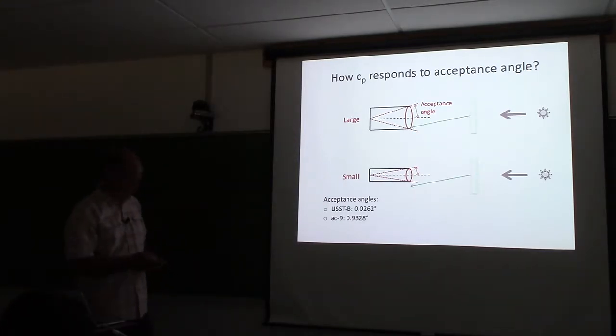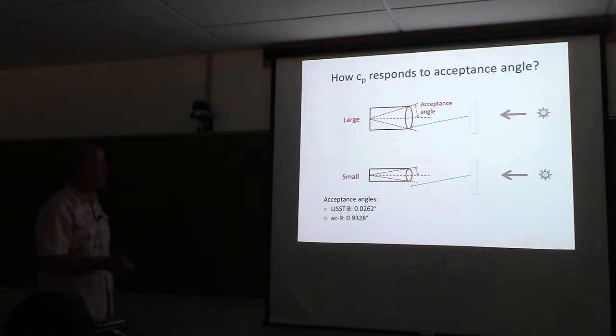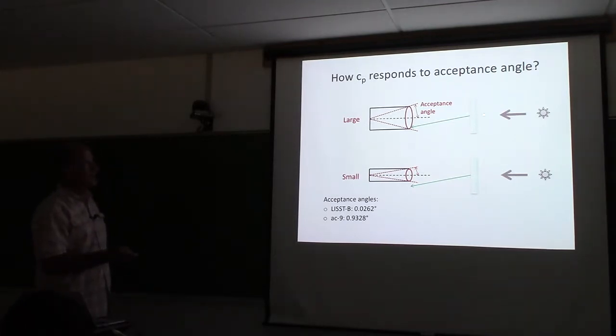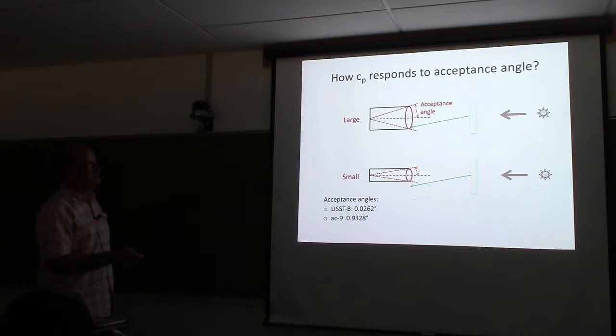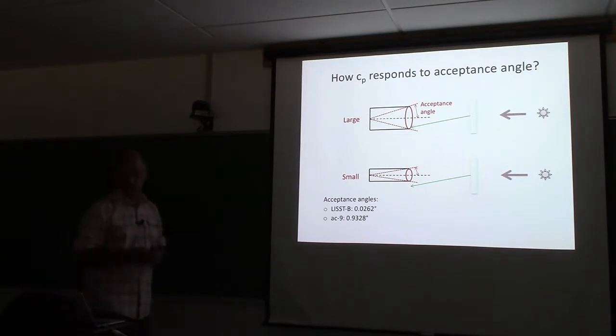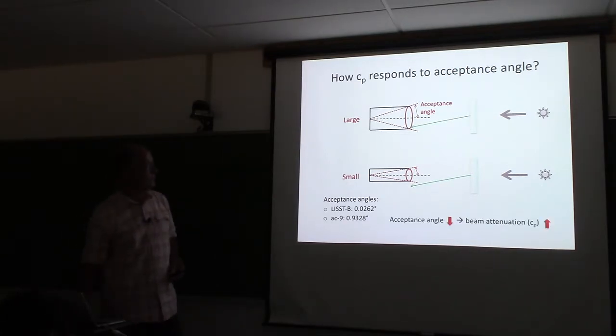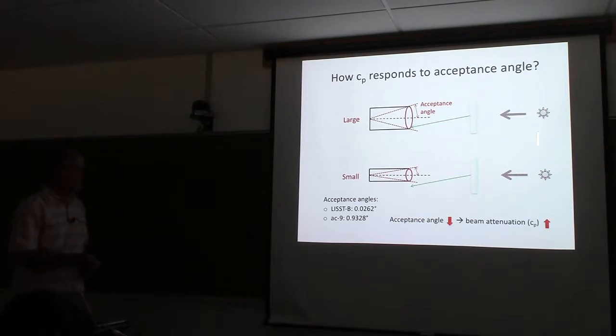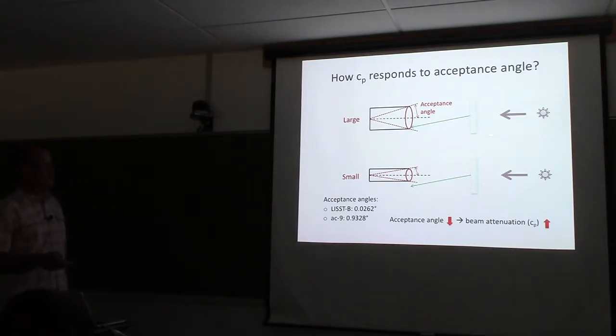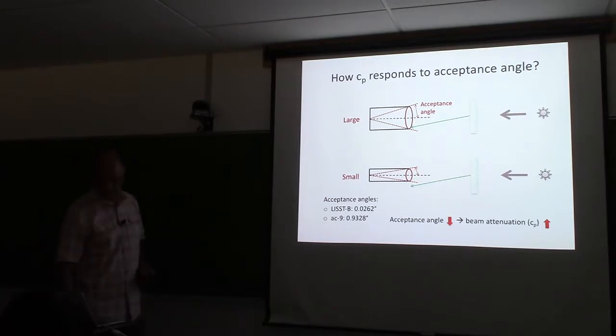If you put in a filament of light and get interaction with a filament of different density water, with the larger acceptance angle instrument the light gets bent a bit but is still viewed as transmitted light. With the LISST, it gets bent a bit and now it's no longer transmitted light. So as the acceptance angle goes down, your interpreted beam attenuation goes up, especially in the presence of these Schlieren.